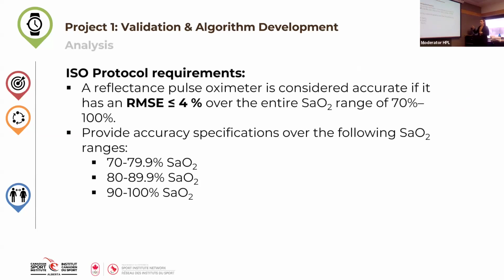So looping it back to the ISO protocol, it itself actually has guidelines for how you can deem a pulse oximeter to be accurate. So their threshold is a root mean squared error of less than or equal to 4%. And then they also want you to provide root mean squared error values for smaller ranges, so not just 70 to 100%, but also 70 to 80, 80 to 90, and 90 to 100% SaO2.